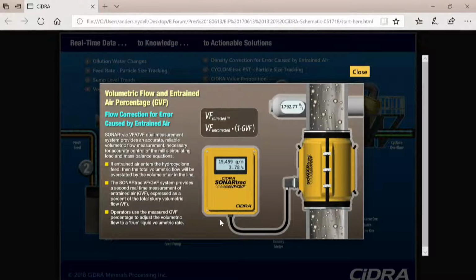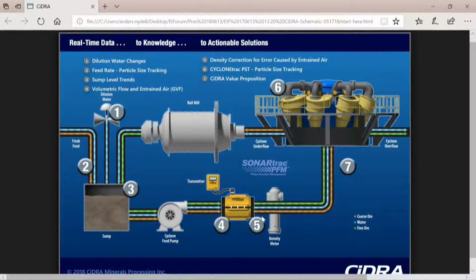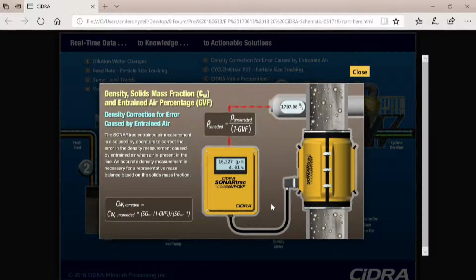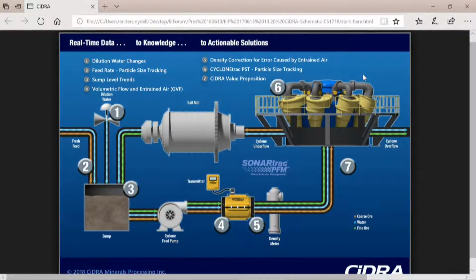These ones we can measure with the CIDRA SONARtrac device that is capable of measuring both the flow and the volume occupied by those bubbles, and then do the correction for the volumetric flow, and after that also simultaneously online the density measurement, so that you will get the real production rate there captured and controlled and stabilized.